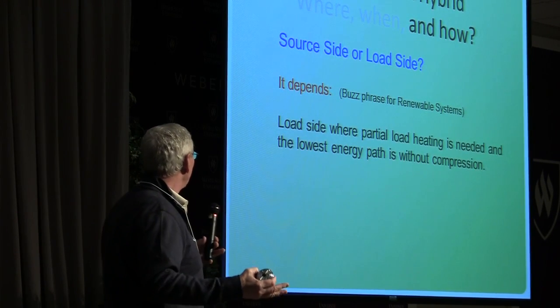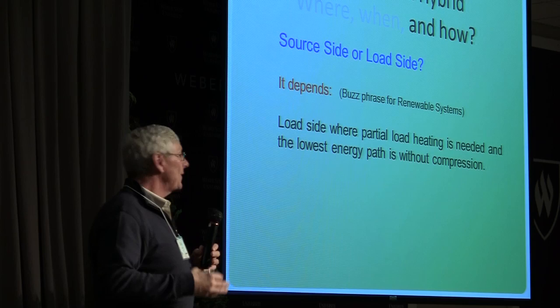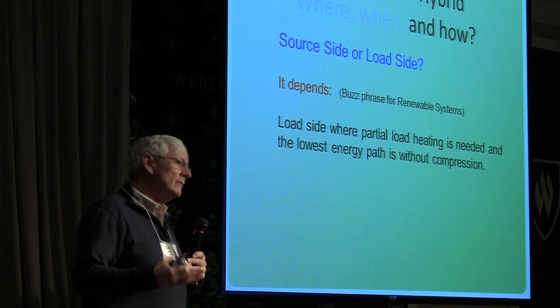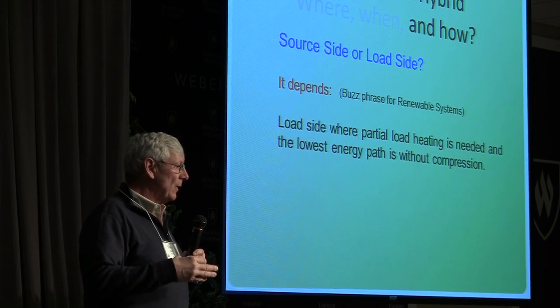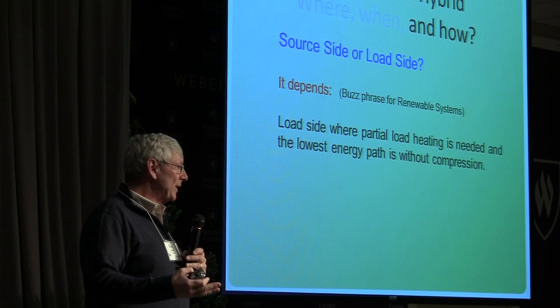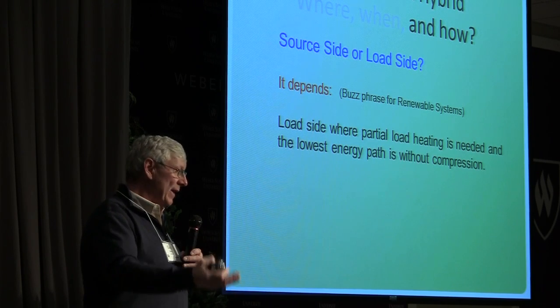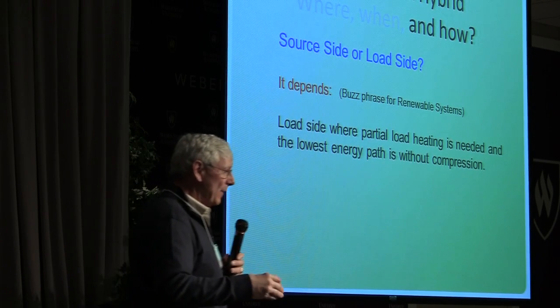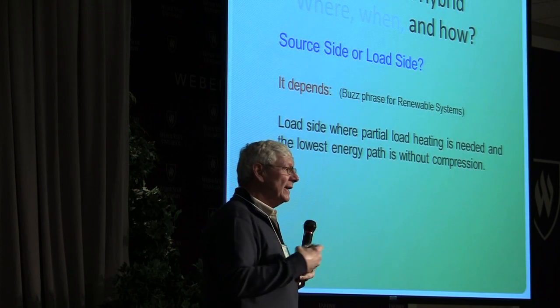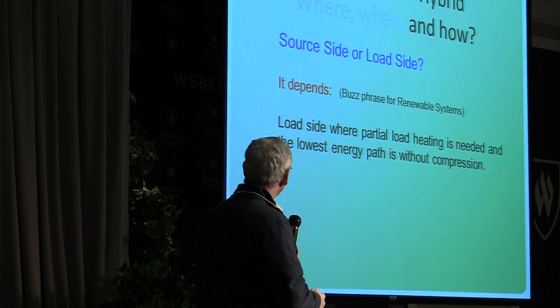On the load side, where partial load heating is needed, the lowest energy path is without compression. We're using the solar energy we stored in that tank. Instead of running the heat pump and running a compressor, we turn over a smaller pump and take a little bit of energy out of that tank, taking advantage of the solar energy we have.